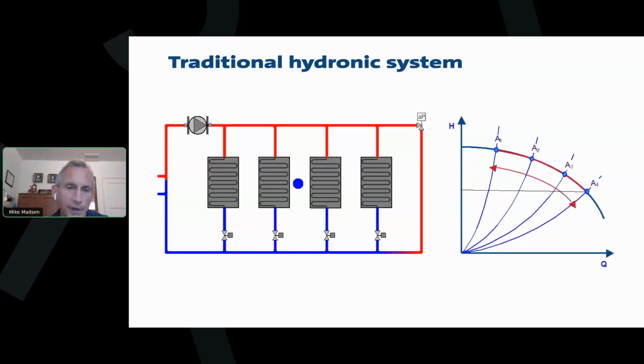Of course, in the old days, VFDs were not cost effective. So we saw a lot of systems like this on the left, where we had fixed speed circulators. We had either some heating loads or cooling loads. We had some control valves and a bypass at the end of the line. And so when there was no load in the system and these control valves were closed off, we would be bypassing a lot of fluid and wasting a lot of energy. So in the old days, we would just let the pump run up and down the pump curve. But now with these smart circulators, with these ECM circulators, with integrated controls, integrated pressure sensors, we can actually apply a VFD on a lot of these applications and get a lot of energy savings.